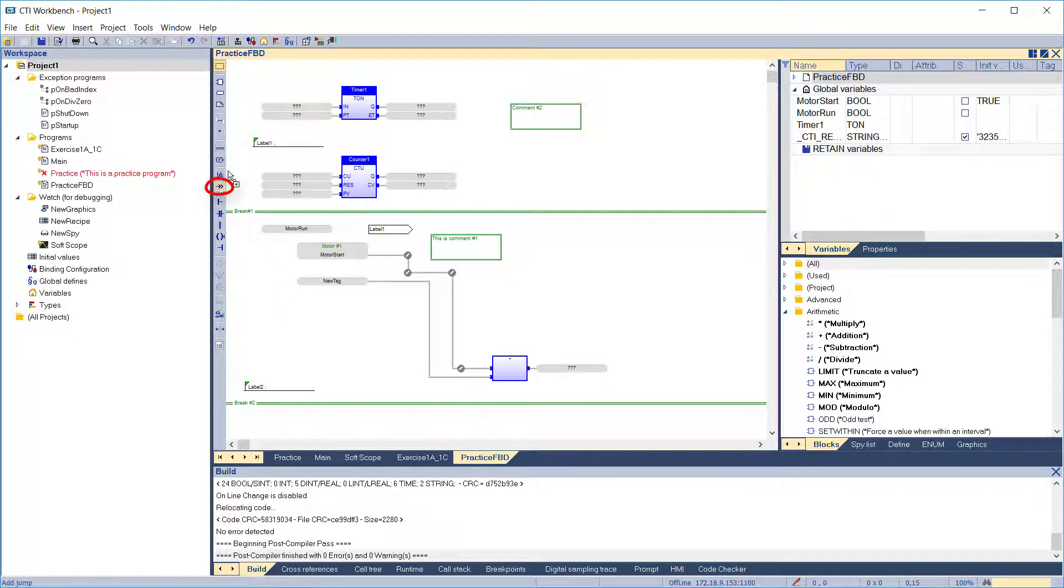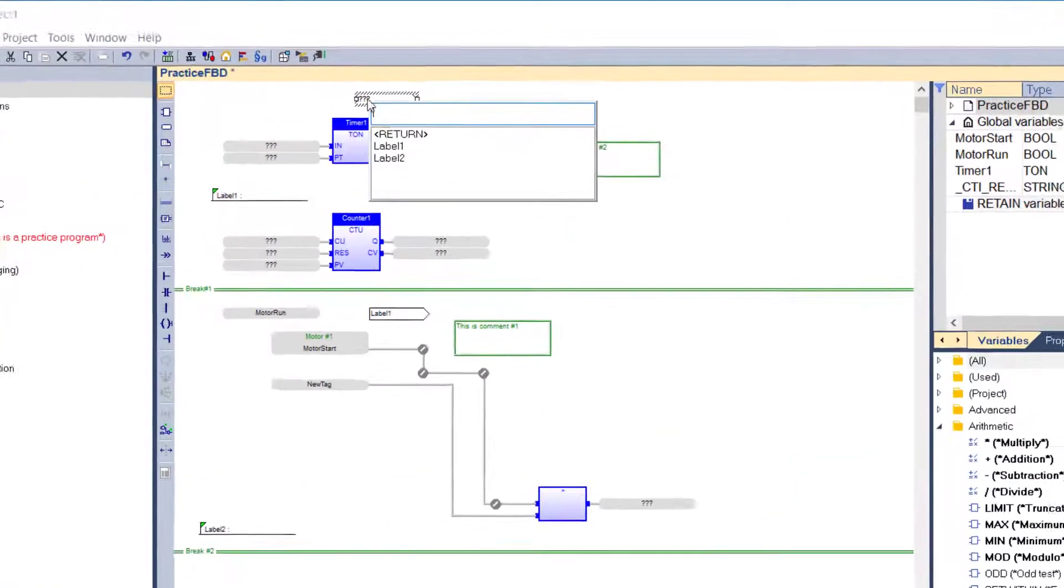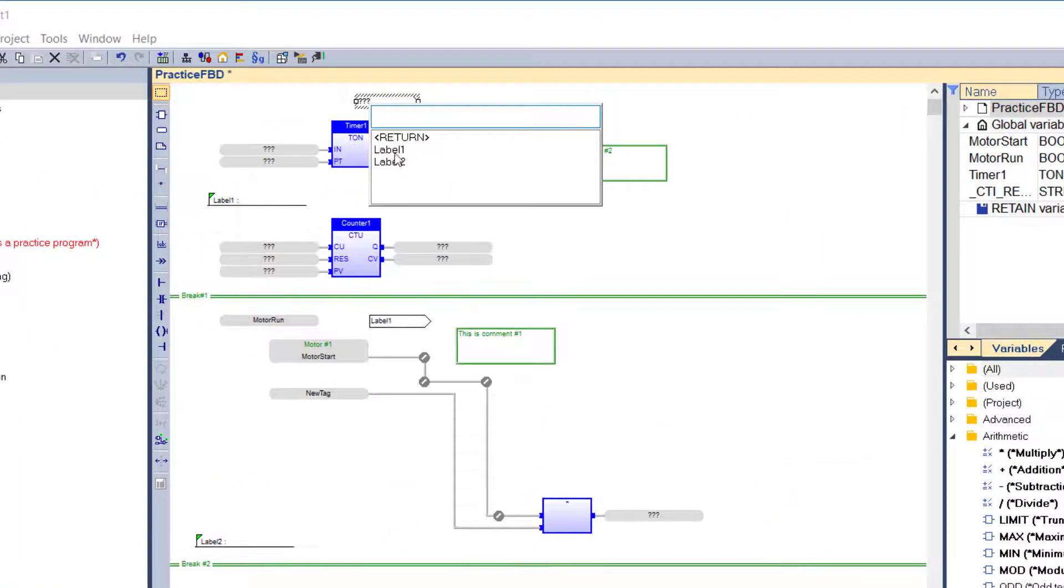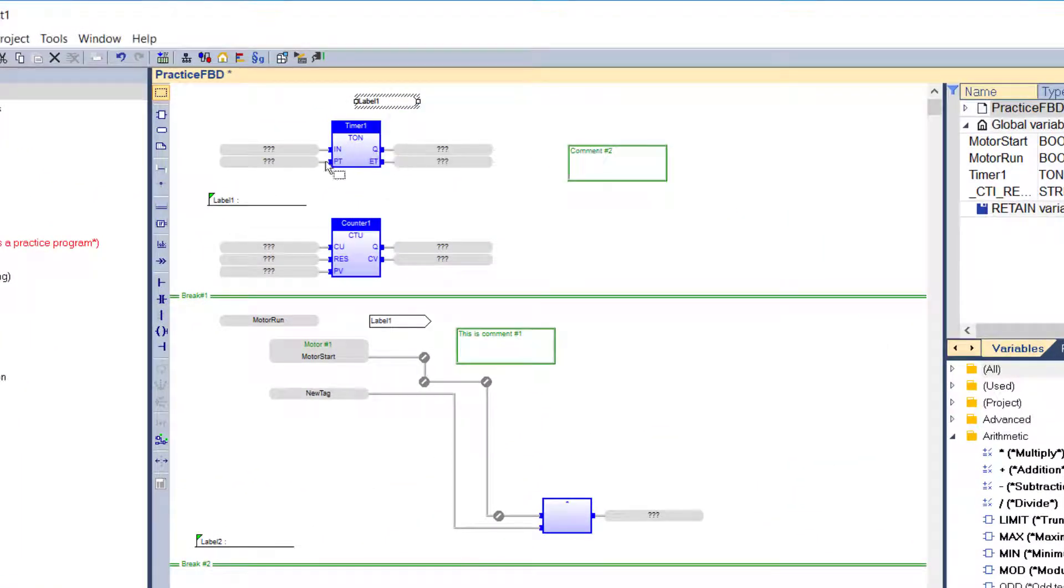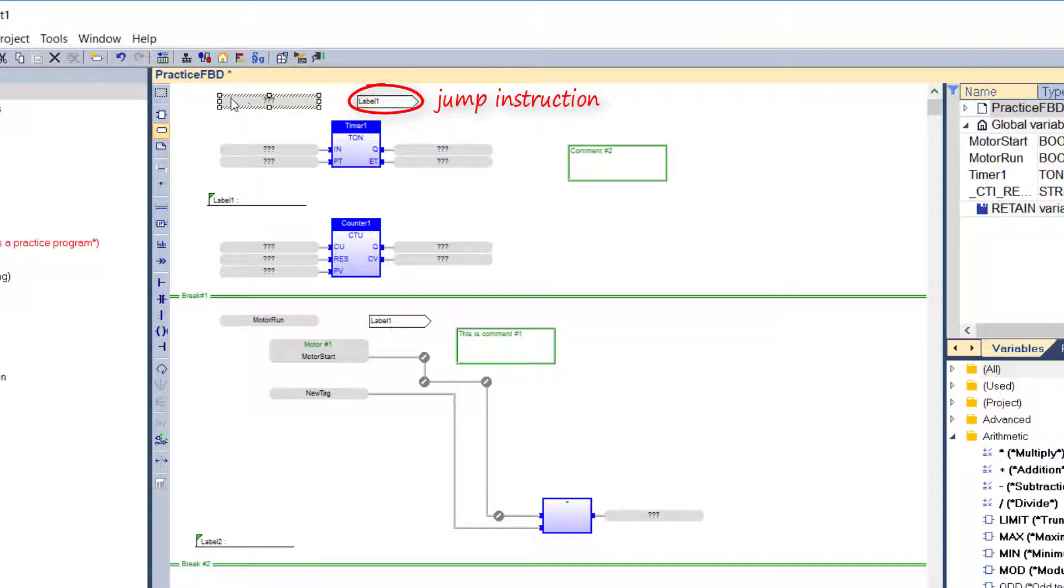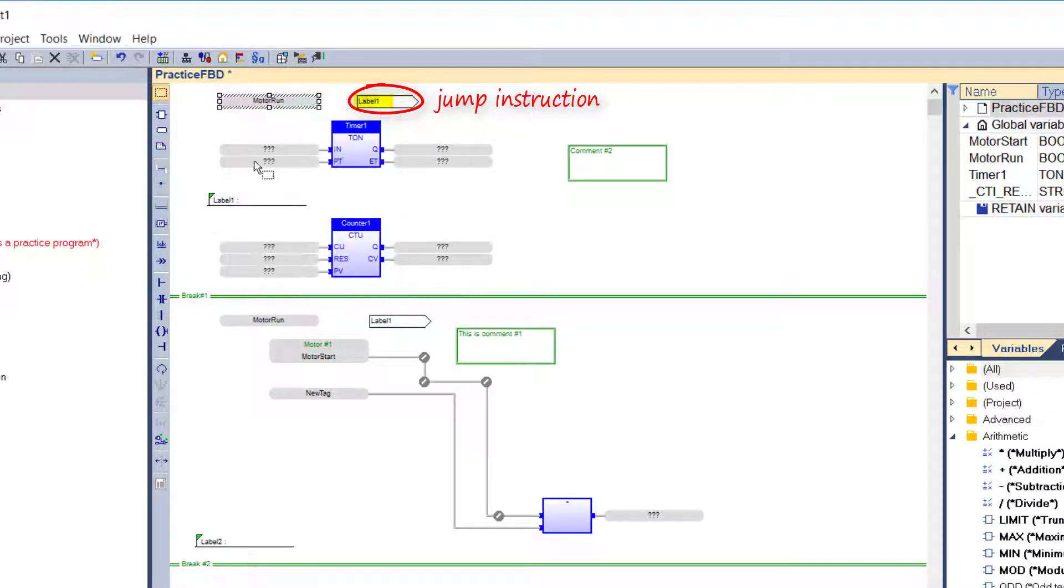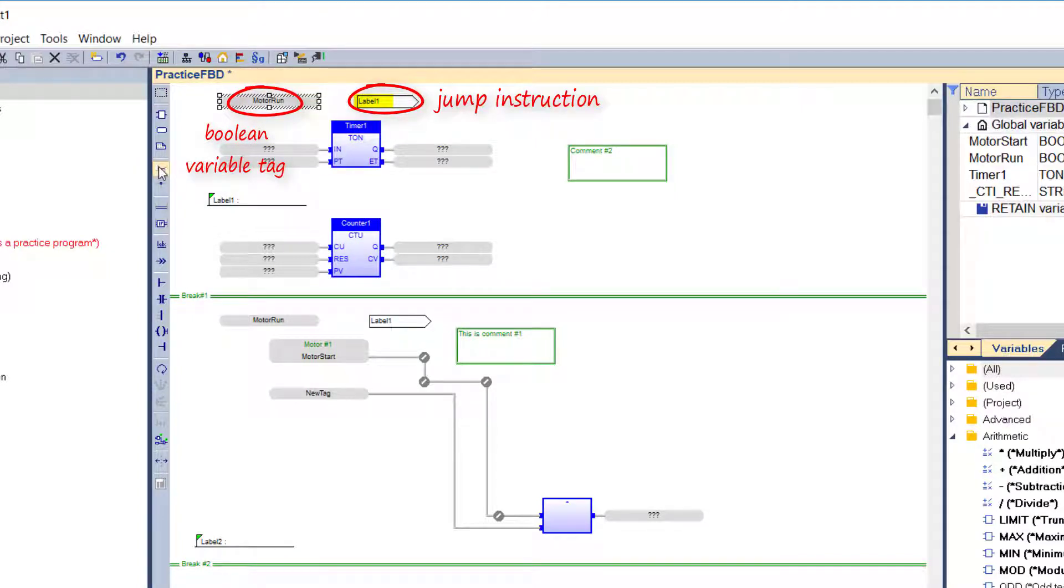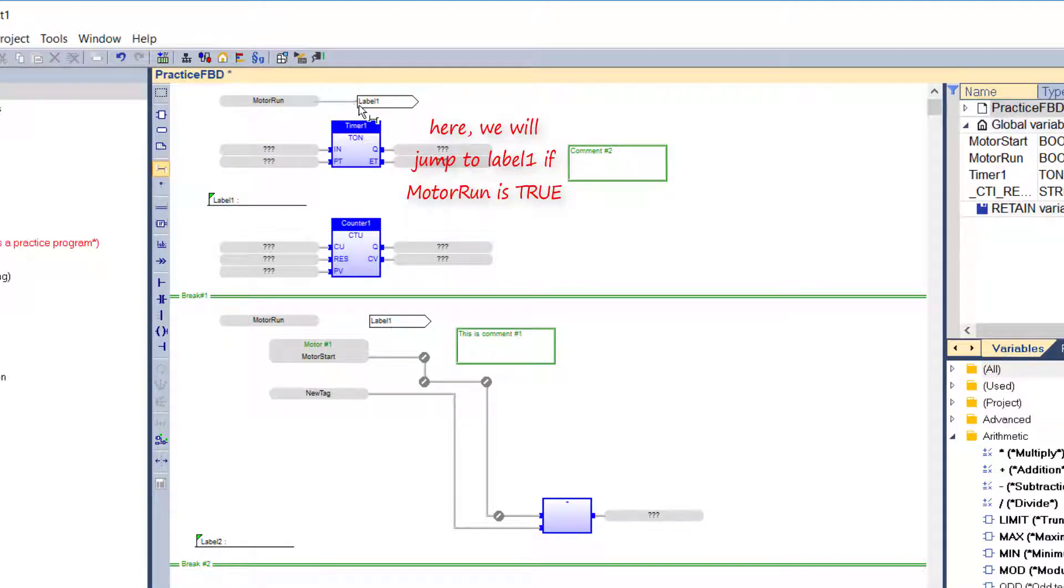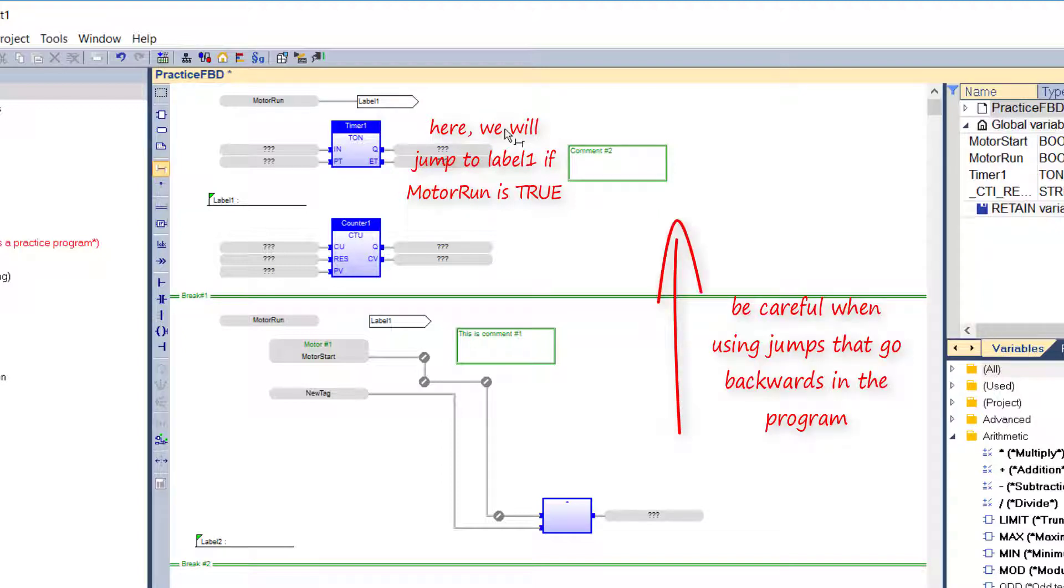A jump to label instruction branches the execution of the program to the point immediately following the specified label. In FBD language, a jump is represented by this symbol with the label name inside. A variable tag precedes the jump, which must be a valid boolean signal. The operation is performed only if the input is true. Use caution when putting backward jumps in your program, as it could lead to infinite loops that block the target cycle.